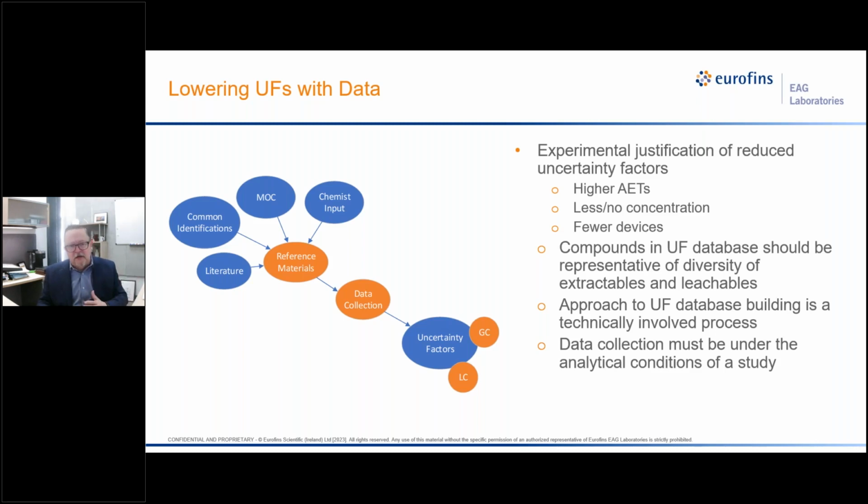Ultimately, you then need to collect the data. And I think one of the things that may sometimes not happen is that people may not necessarily collect that data under the same conditions that they're running extractable studies. So, you want to have a nice multi-point curve. You want to be able to evaluate the linearity of that curve. You really want to know that you're collecting the data under the best case scenario using a validated method so that you can depend on that data long term.